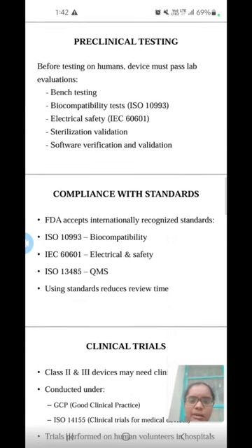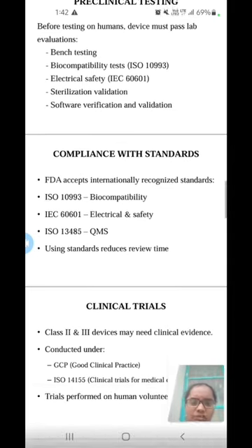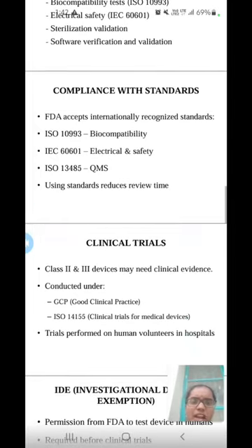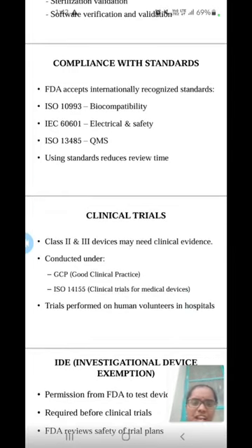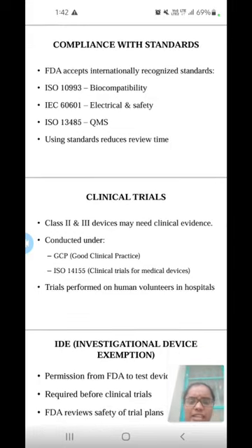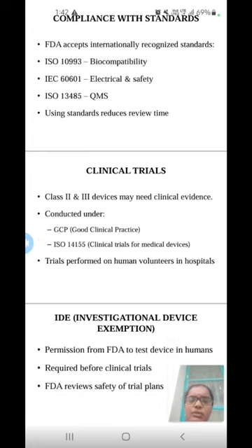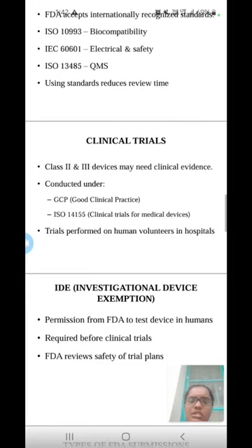Preclinical testing: before testing on humans, the device must pass lab evaluation, bench testing, biocompatibility tests, electrical safety, sterilization validation, and software verification and validation. Compliance with standards: FDA accepts internationally recognized standards, ISO 10993 for biocompatibility, IEC 60601 for electrical safety, and ISO 13485 for QMS. Using standards reduces review time.